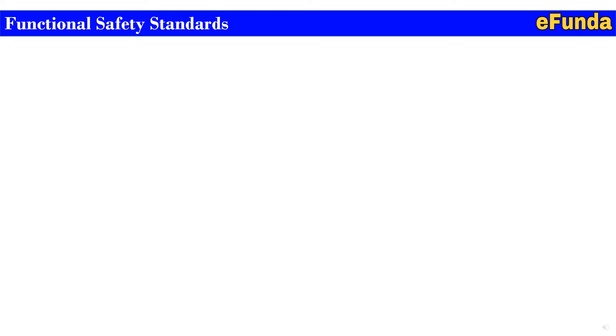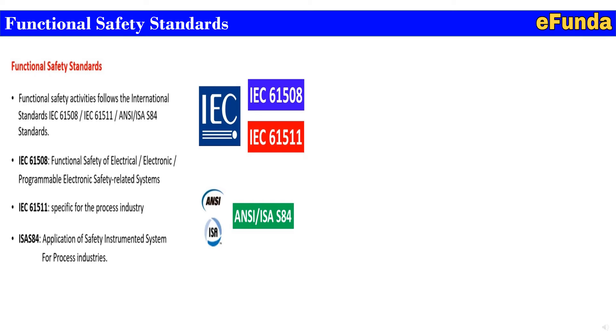The SIS will have a SIF which might include a pressure transmitter to sense when an intolerable pressure level is reached, a logic solver to control the system logic, and a solenoid valve to vent the contents of the vessel to a safe location such as a flare stack or storage tank, thus bringing the pressure vessel to a safe state. For this, one can refer to the picture below where IEC 61508, IEC 61511, and ISA S84 are shown as the relevant functional safety standards.